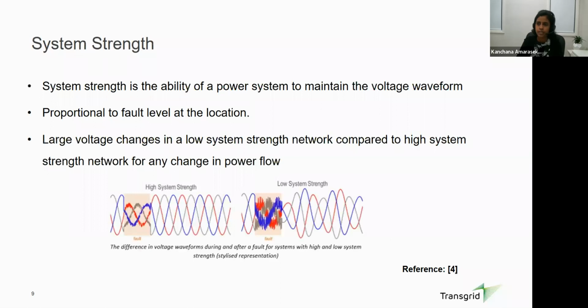So the first network service is system strength. System strength is defined as the ability of a power system to maintain its voltage waveform. The normal voltage waveform of a power system will look something like this. And the system strength is proportional to the fault level of the location. Usually, if the fault level is high, we say the system strength is high. If the fault level is low, we say system strength is low. One of the characteristics of a system with low system strength is that we see large voltage changes for any change in power flow. For example, if we switch a capacitor bank or an inductor in a network with low system strength, we will see large voltage changes.